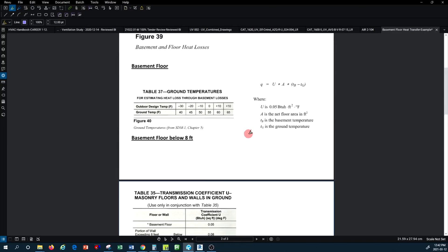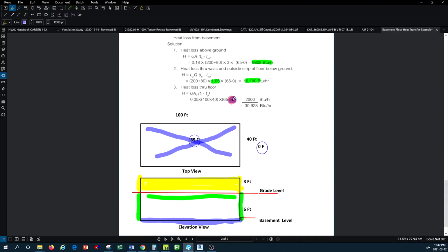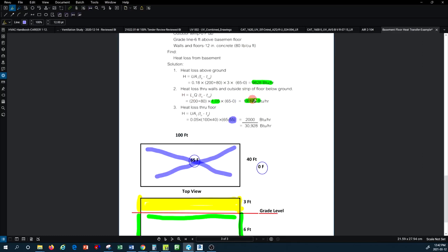From the table: when the outdoor temperature is 0°F, the ground or soil temperature is 55°F. So you plug 55°F into the floor equation as the ΔT reference (inside space is still 65°F, soil is 55°F) and calculate the heat loss through the floor. The sum of all three heat transfers — above-grade wall, below-grade wall, and floor — gives you the total basement thermal load. Thank you for watching; please subscribe and press the notification button to see future tutorials, and press like if you enjoyed this one.